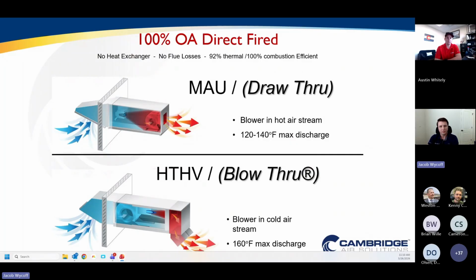So as opposed to this top example, the draw-through style makeup air unit that we talked about previously with our M series heater, we have a different offering for these space heating applications. We call that our S series heater. It's a high temperature heating and ventilation unit, or HTHV. How that differs from a draw-through style makeup air unit is that the blower is actually moved upstream of the burner into the cold air stream, which has huge implications whenever you're talking about heating a space efficiently, because it allows us to increase our discharge temperature all the way up to 160 degrees.